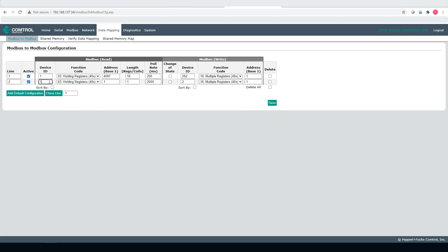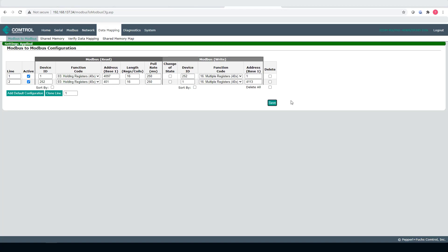Also, the next thing is the reverse. 252 holding registers from 401, 16 again, 250 milliseconds. And then here, device ID 1, 4113. Choose save.